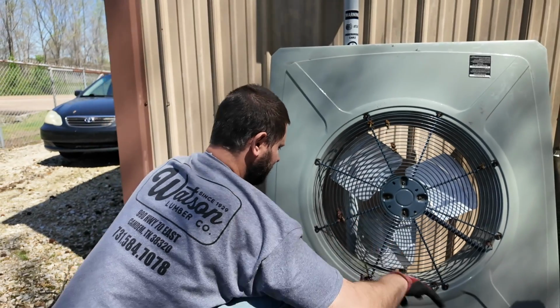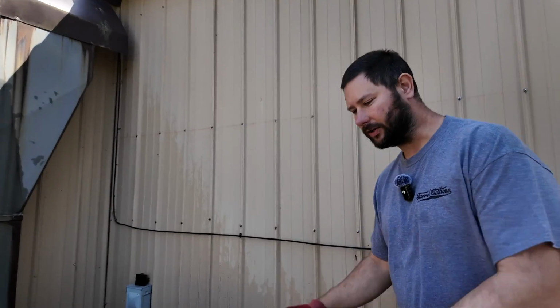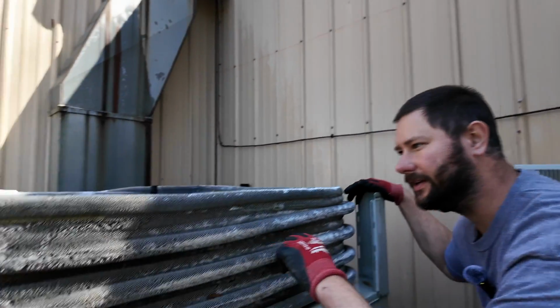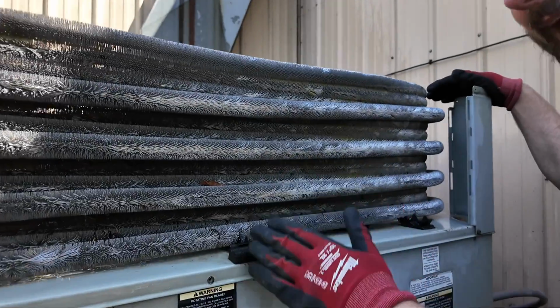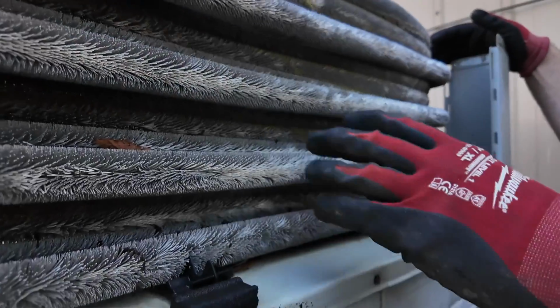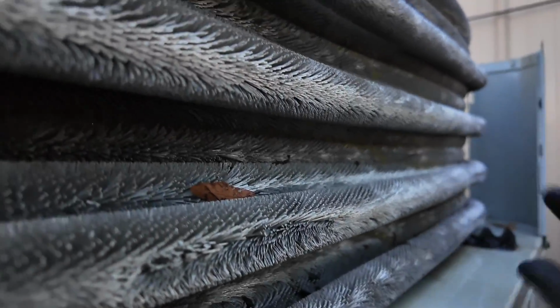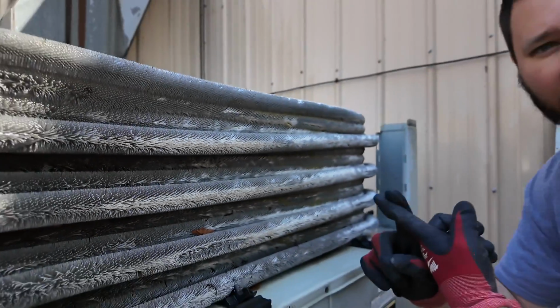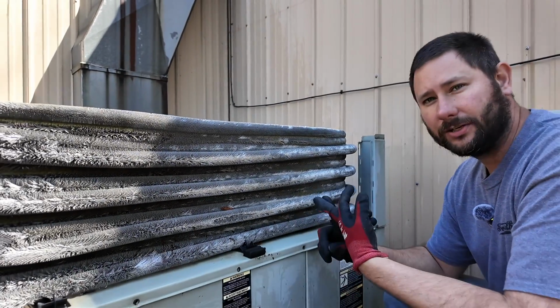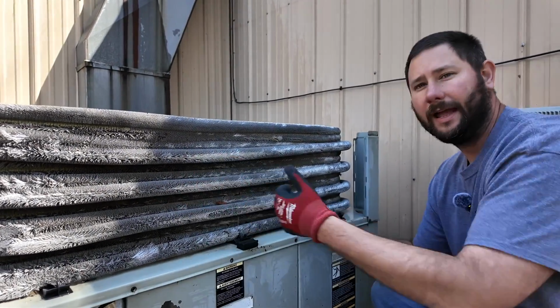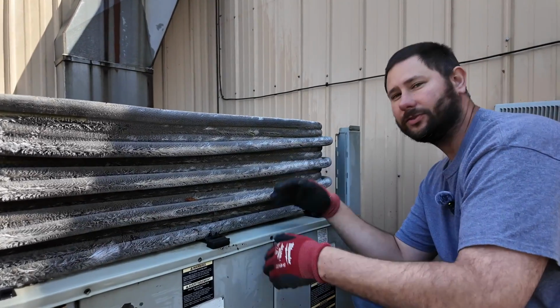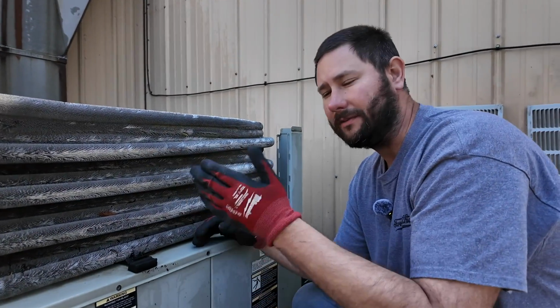That looks good. Be careful when you're washing a coil like this one. This is a spine fin coil. It can easily be damaged. You can end up bending the fins on this coil and other aluminum coils. Make sure you never use a pressure washer. And make sure that you go slow and you don't go at an angle, just go straight through. That way you have less of a chance of damaging the coil when you're cleaning it.